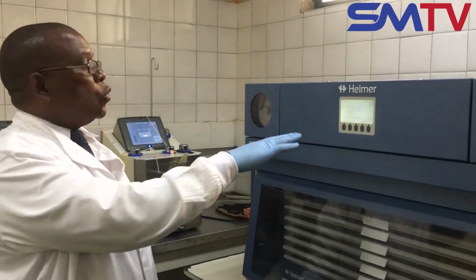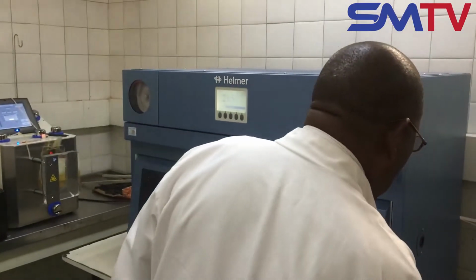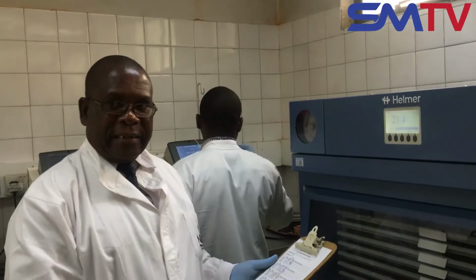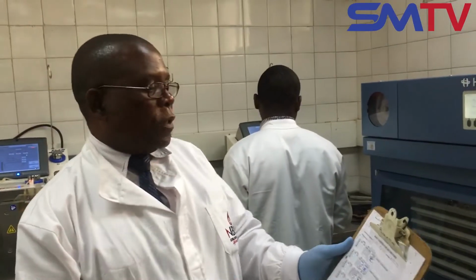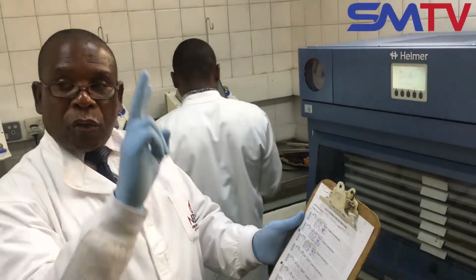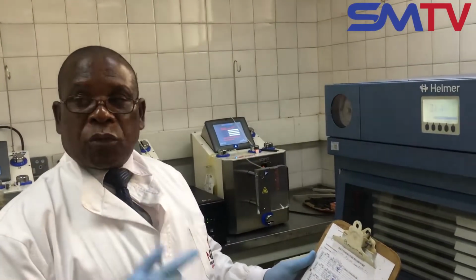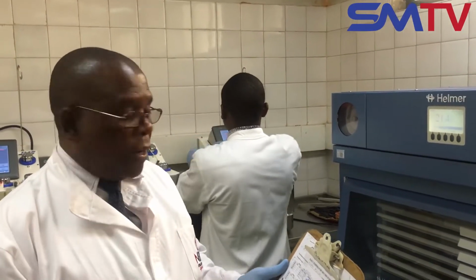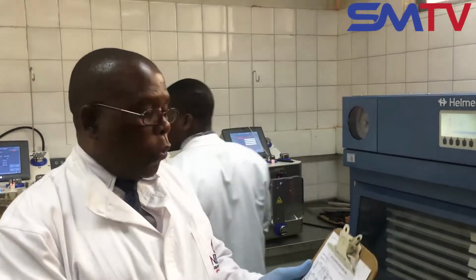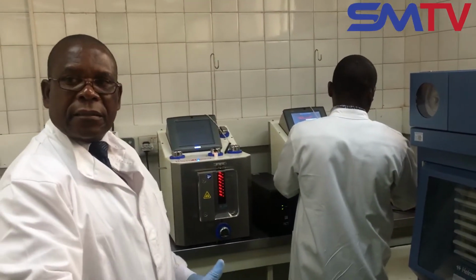I talked about 22 plus or minus 2, as you can see, it is 21.3. And we monitor these temperatures religiously. If you check here, we've got a daily temperature record where we take the temperature at 8 o'clock, at 2 o'clock, at 1700 hours, and 12 midnight, because the laboratory operates 24 hours. So there's someone who actually comes and takes the temperature at midnight. We monitor these temperatures religiously, and we keep the platelets agitating to prevent aggregation, like I said.